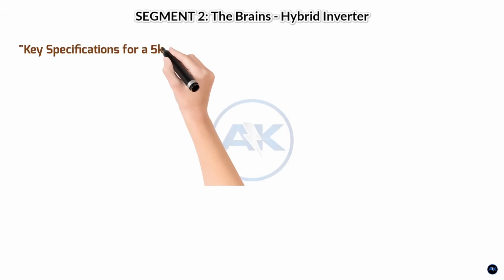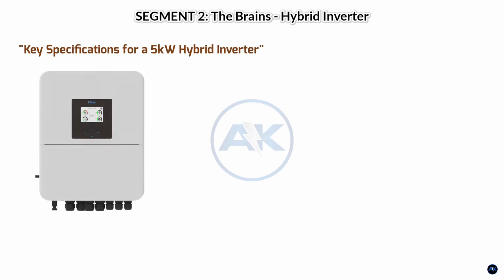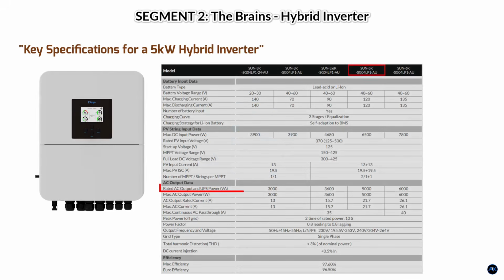Key specifications for a 5 kilowatt hybrid inverter. Rated power output: 5,000 watts or 5 kilowatts. Continuous output: this is the maximum AC power it can supply to your home. Surge power, often double the rated power for a short duration, 10,000 volt-amps for a 5 kilowatt inverter, allowing it to handle sudden power demands from appliances.